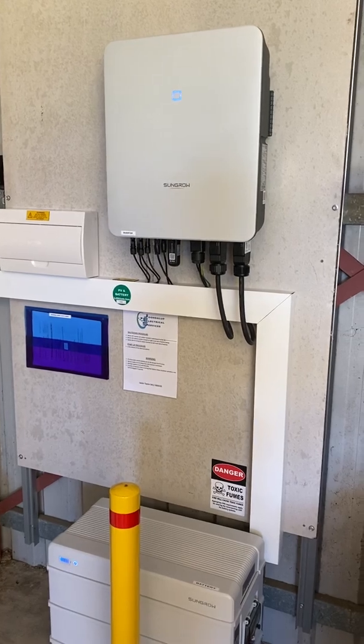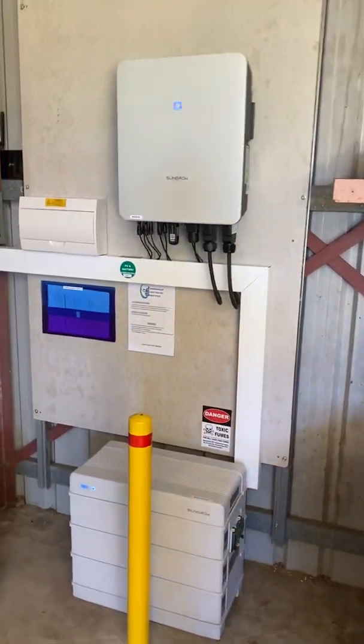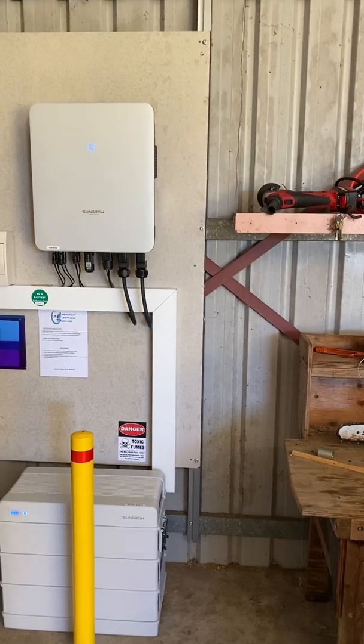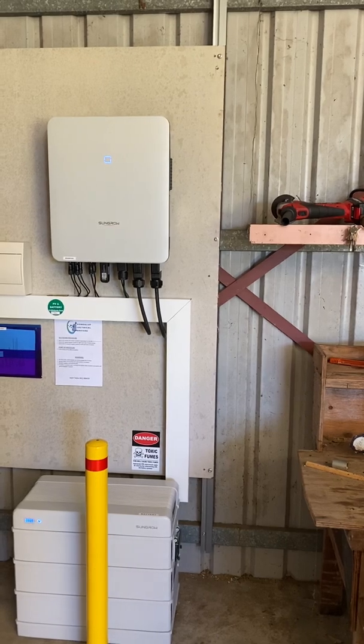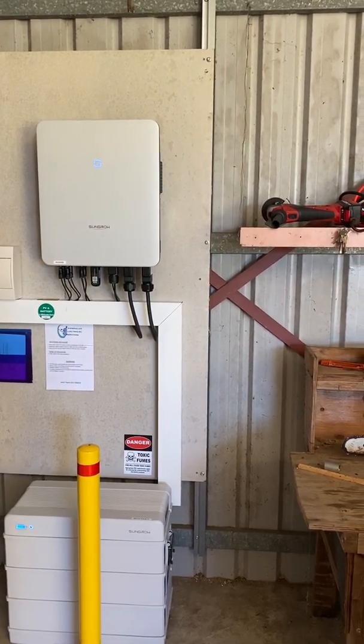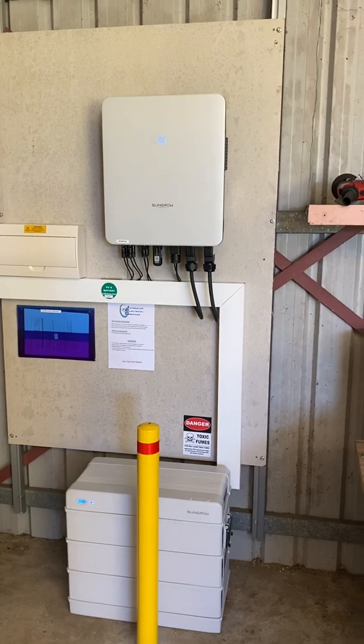The last full three-phase backup system I did was the Fronius Gen 24, but unfortunately that was a nightmare to install. There's also about a 20-second delay between the grid dropping out and backup power coming on, which kind of defeats the purpose. I think this SunGrow is a far superior setup.